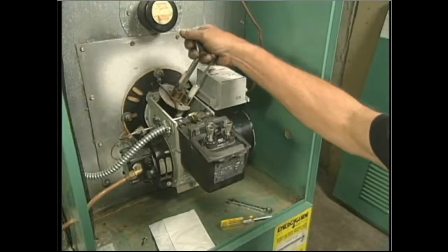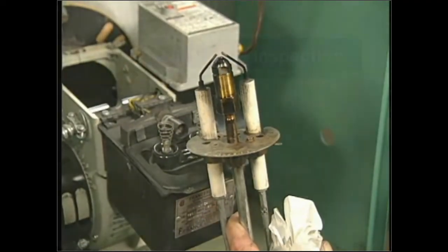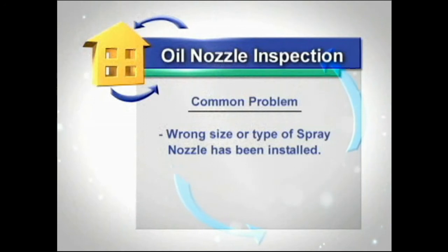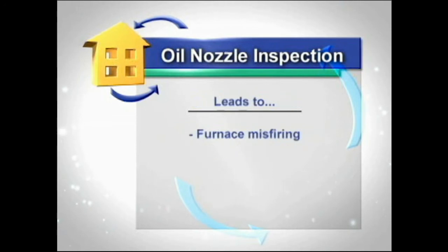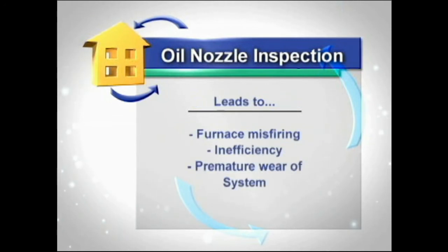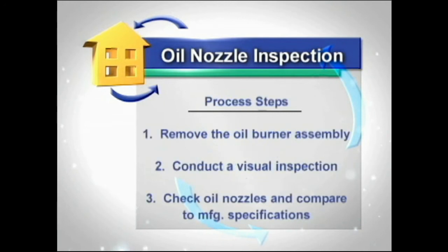Depending on your agency's protocols for oil furnace testing, an additional procedure involving the removal of the oil burner assembly and inspection of the oil nozzles should be considered. A common problem found with oil furnace burners is the wrong size or type of spray nozzle that is installed in the oil burner, which can lead to misfiring, inefficiency, and premature wear of the system. The following steps provide an overview for removing the oil burner assembly, conducting a general visual inspection, and checking the oil nozzles to make sure they meet the manufacturer's specifications based upon the heat loss calculations for the home.